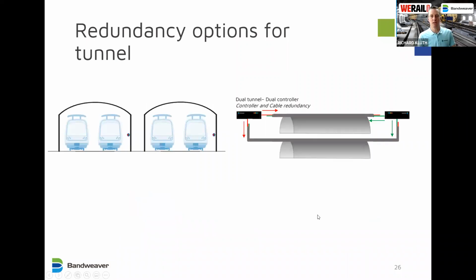If we move to an example with 2 tunnels, still with the 2 controllers, you have the same controller and cable cut redundancy. So these 2 controllers are still monitoring this top cable here, but now they've got a second tunnel, second cable with a second channel on each controller. So as you increase the number of channels, you can increase the redundancy operations. So in this case, we have two controllers, 2 tunnels, so 1-to-1.